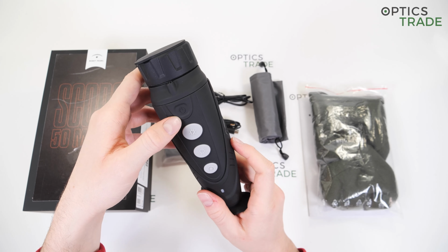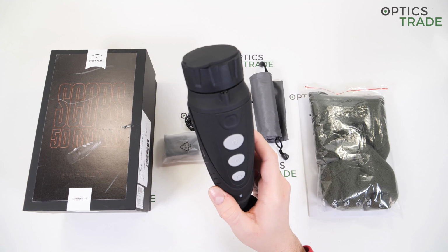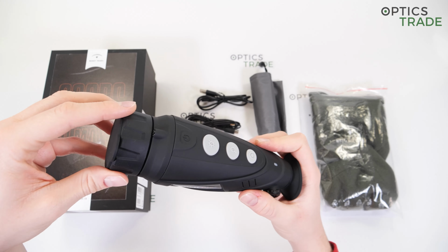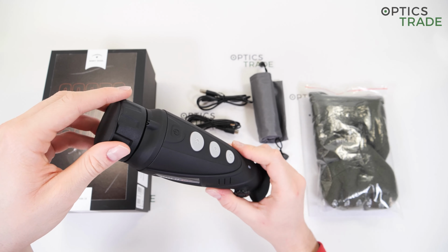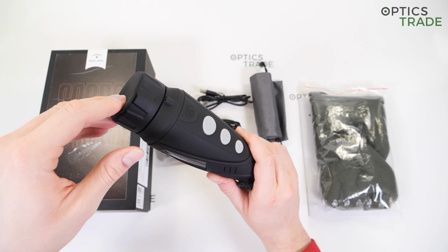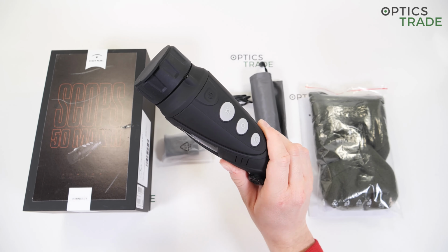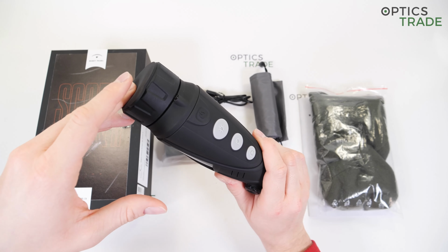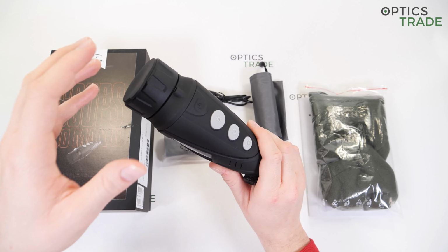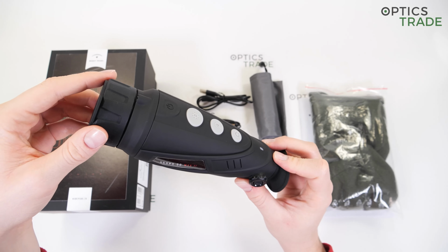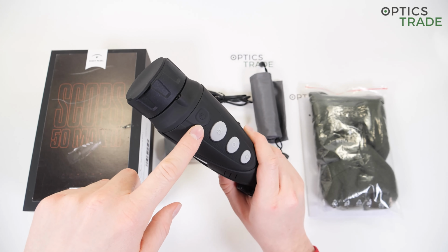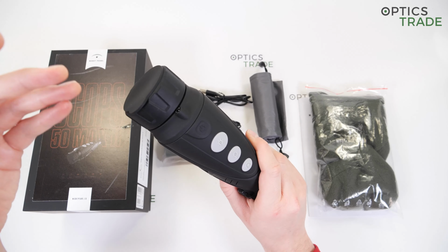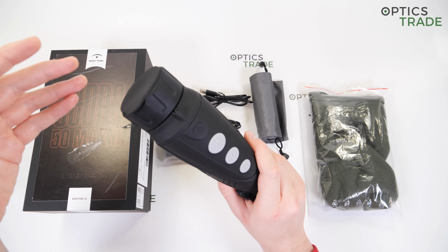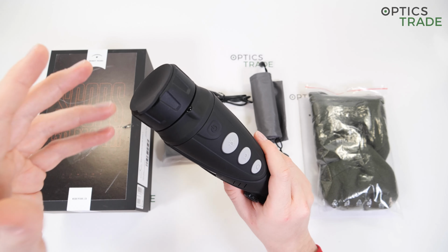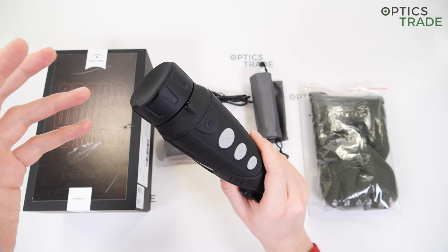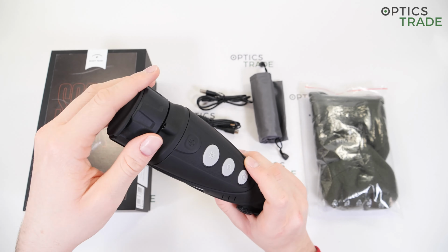You switch on the device by holding the power button for 3 seconds. It has a 10-second startup time, which is quite long. You switch it off the same way. If left turned on, it will turn off automatically after 20 minutes to preserve battery life. When the device is turned on, you can also enter the standby mode if you press the power button. In this mode, the display is turned off, providing additional cover from the nearby game. But if you wish to go back to normal mode, it only takes 1 second, so that is really quick.